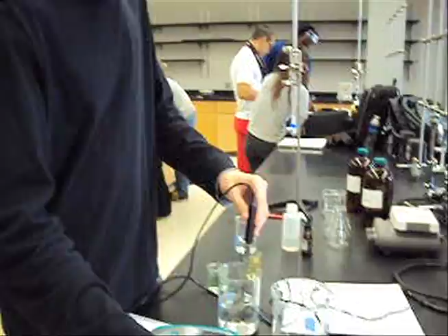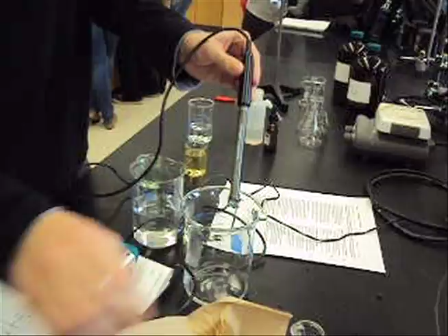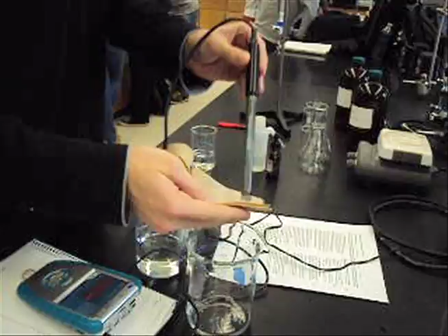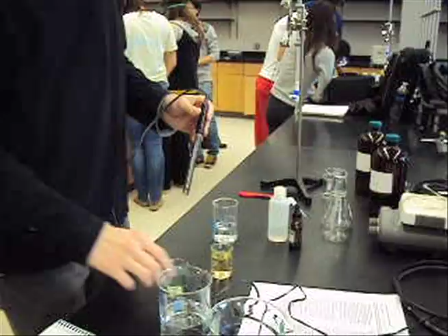Doing the calibration of the pH meter for titration. First, you have to make sure that it's always hydrated because it needs to have selectivity when it's going for hydrogen ion detection. So what you do is you take it out of the water, rinse it off to make sure, gently blot it. Because if you rub it too hard, it will knock out calibration even more and damage the instrument.